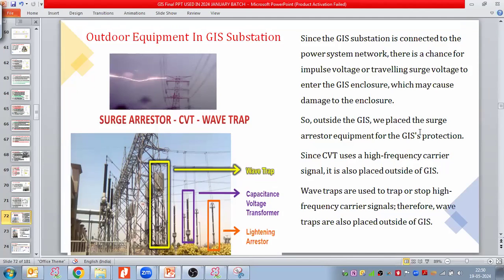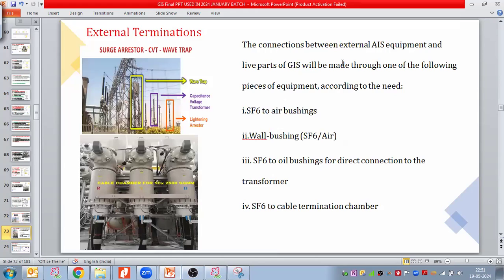So outside the GIS, we place the surge arrestor for GIS overvoltage protection. Since the CVT uses high frequency carrier signals for carrier communication, it is also placed outside the GIS. Wave traps are used to trap or stop high frequency carrier signals, so the wave trap is also placed outside the GIS. So the surge arrestor, CVT and wave trap, plus the transformer, will be outside, and we require terminations between the GIS and AIS equipment. The connection between the external AIS and the live part of the GIS will be made through one of the following pieces of equipment, according to the need.